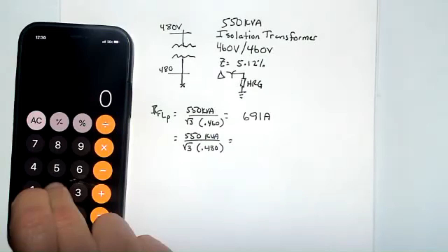what you have to remember is kVA is a capacity thing. It's volts and amps together. So if we run at a lower voltage, we could go up to that amp capacity rating. If we run at a higher voltage, we're likely going to only want to put up to that many amps through it. Otherwise, we're going to exceed the kVA rating of the transformer. So that's why these two numbers are important to understand.